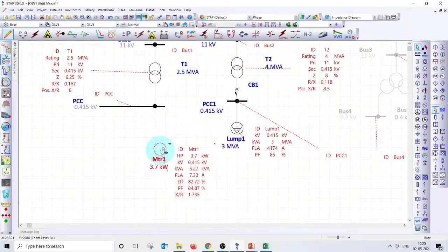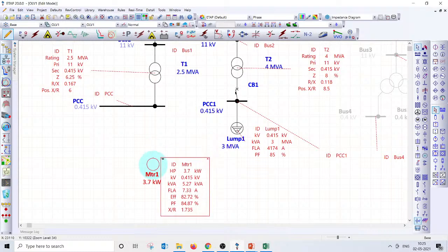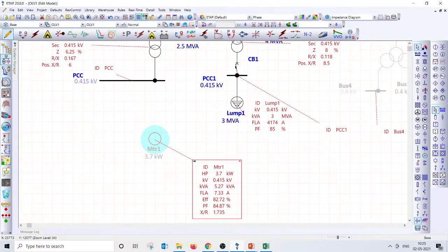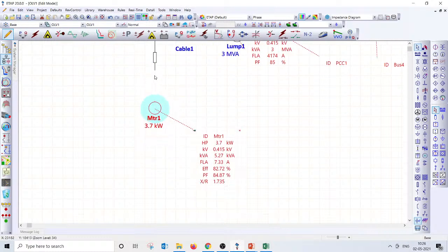Okay, fine anyway. If you look at the full load current, the full load current is 7.33 amps. And for 7.33 amps, what could be the approximate cable which you can put up? What should be the approximate cable length which you need to consider for a current of less than 8 amps?